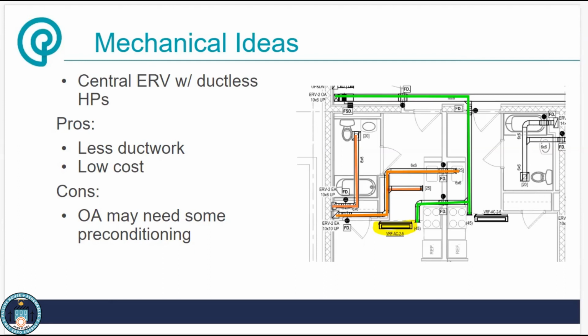But on a lot of the multifamilies, especially out in New England, we're seeing a ton of centralized ERVs just driving that. I think James's data showed that, where we've got a centralized ERV on the roof and it's going to supply outdoor air in the green to each of these units. And then there's another exhaust riser that runs back up to that ERV in orange that's going to pull all of the exhaust air from the kitchen and the bathrooms.